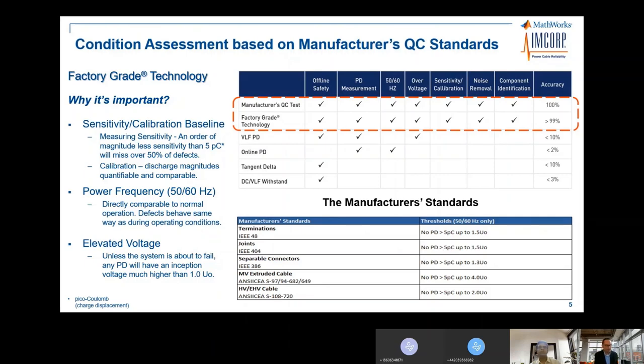But how do you do the same thing in the field? In the field, you don't have a Faraday cage or EMC chamber. You need equipment that excites the cable at 50 or 60 Hz, removes the noise, and can calibrate to the specific standards as manufacturers do. It is very important that the measurement is as close as possible to the actual operating conditions.